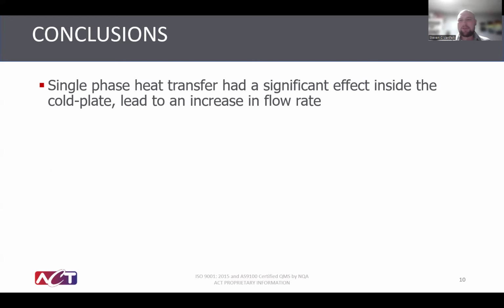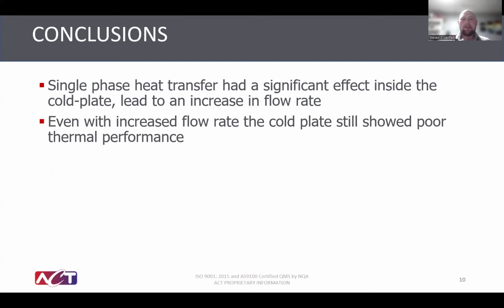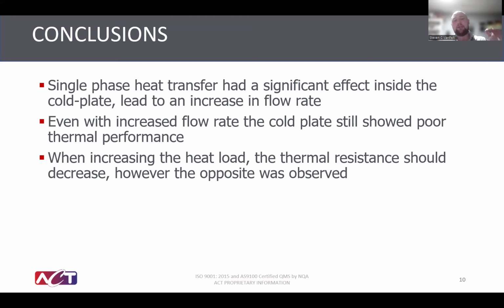Even with that higher flow rate, we were still seeing poor thermal performance. Normally, as you increase the heat load on a cold plate, the thermal resistance should decrease. Instead, we observed it leveling off and then doing the opposite. So we had to think about what could have caused this.